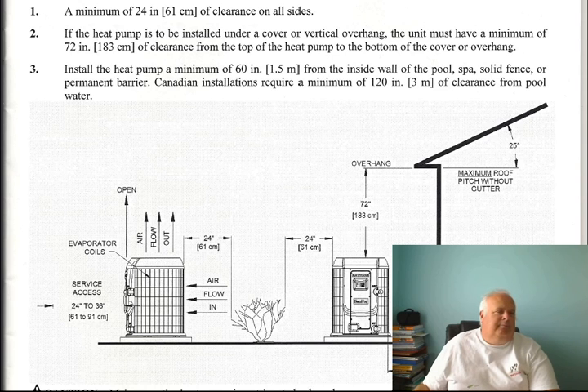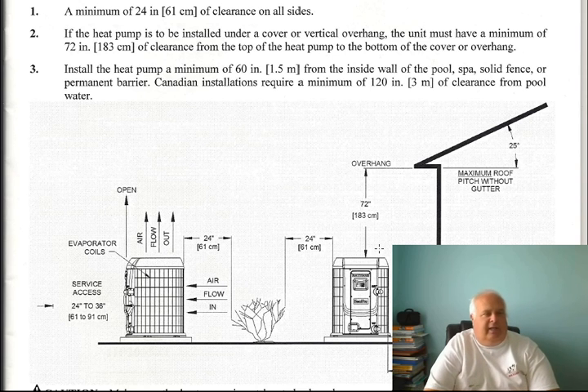I want to touch on one of my pet peeves on installation. We have a roofline - house, garage, whatever. The reason why you don't want to be near the roofline is when it rains, the water comes down. So if you had this heat pump here and the heat pump was on, the amount of water running off your roofline will either slow down or bend your blade.